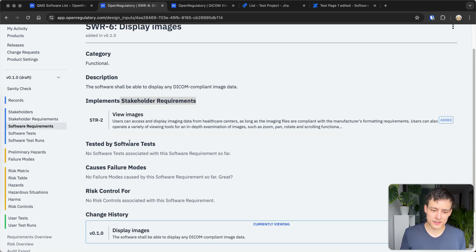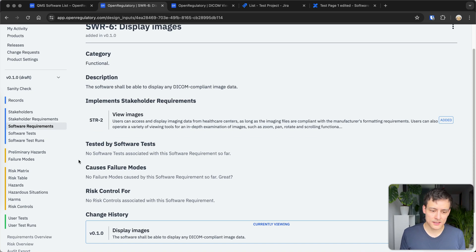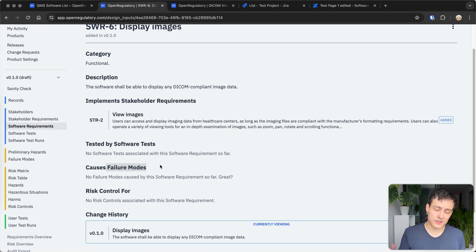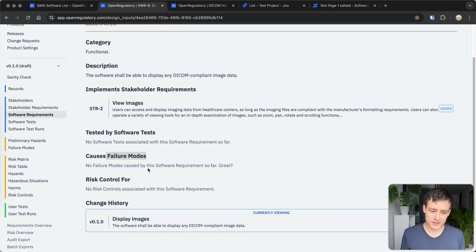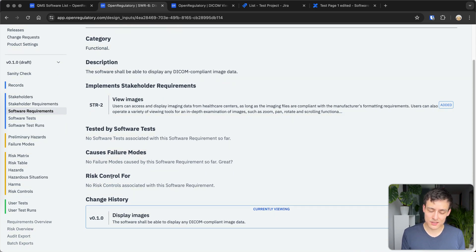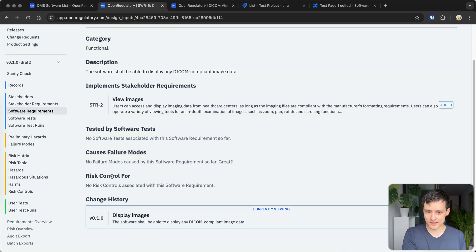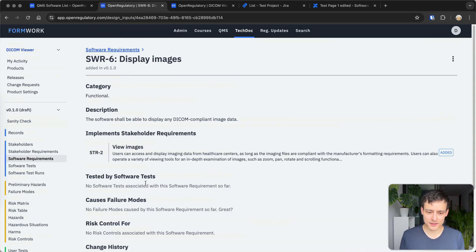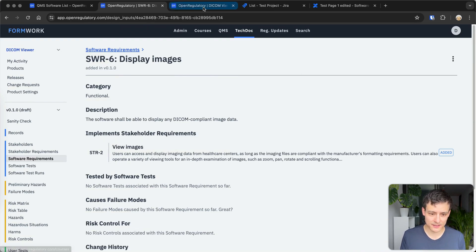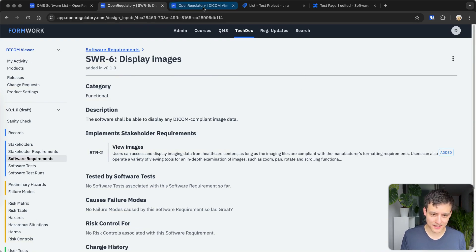That's a regulatory requirement. So you need to define something which is called stakeholder requirements or user needs. You need to link it to software tests, so you have to show you've actually tested it. You need to link to failure modes to do a risk assessment of what can go wrong if this feature fails. And you can link it to risk control. So it could actually be something which reduces a certain risk. I won't go into too much detail here, maybe in another video.